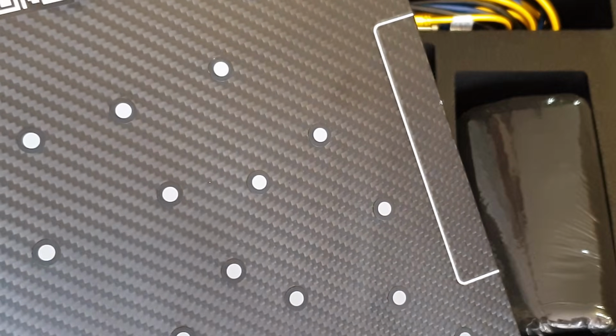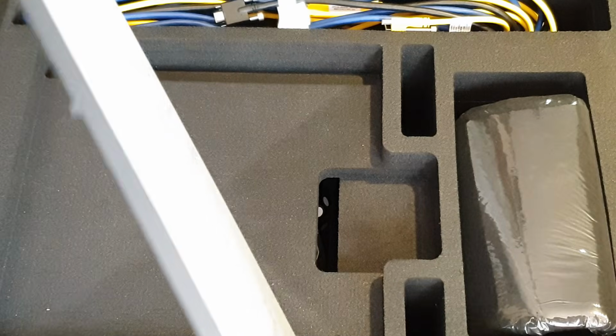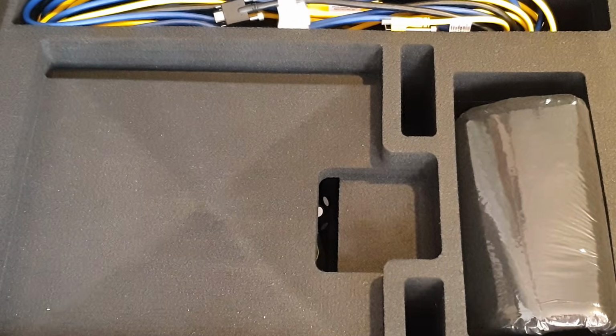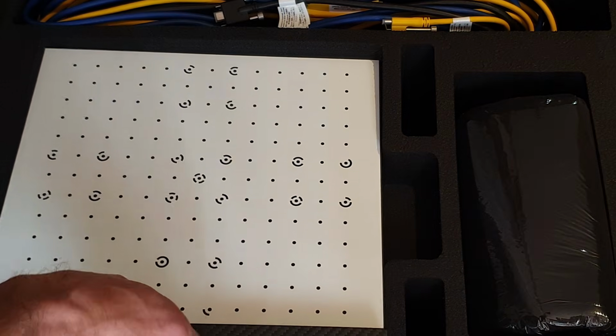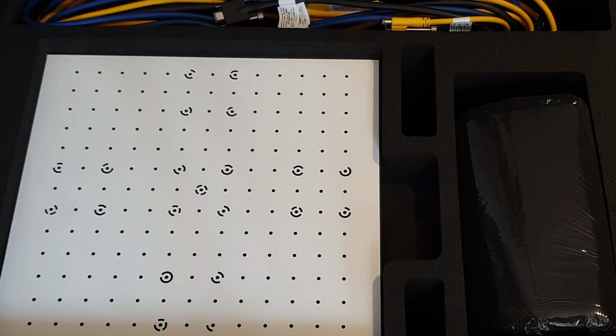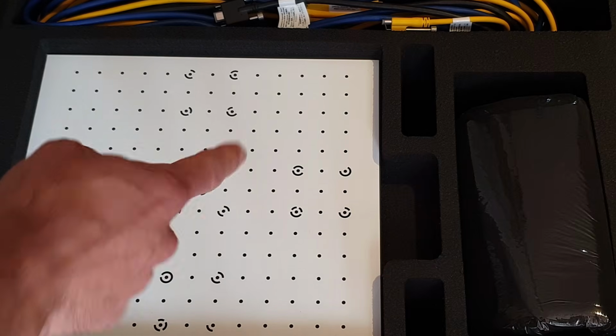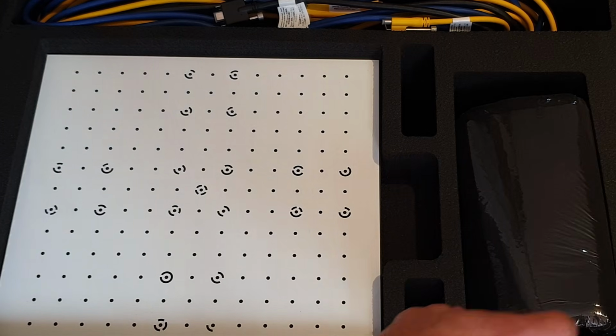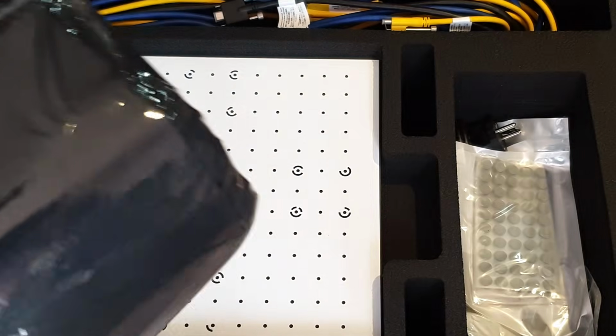Here's the other side of the calibration plate. It's made of carbon fiber. And I don't know what the surface material is. Ideally, it should be aluminum oxide. But it's probably too expensive for this scanner. Yeah, but that's one thumb down at this moment for not putting any sort of protection over what is the most important part of this scanner. Without this calibration plate, you're basically not going to be scanning.